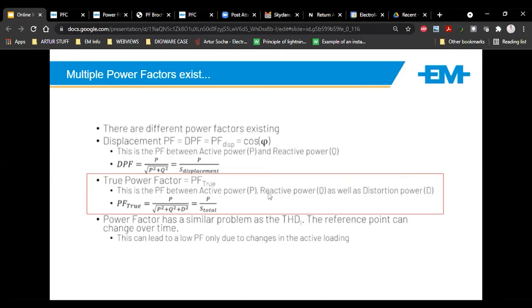What is true power factor? It's a combination of the cos phi and what we call distorted power. That's what we're going to get into now, just briefly, on what harmonics are. Harmonics in your system will also affect your true PF. Your council is most likely looking at true PF, depending on the utility meter. So don't make the mistake: a normal power factor system only corrects DPF, cos phi, not true PF.